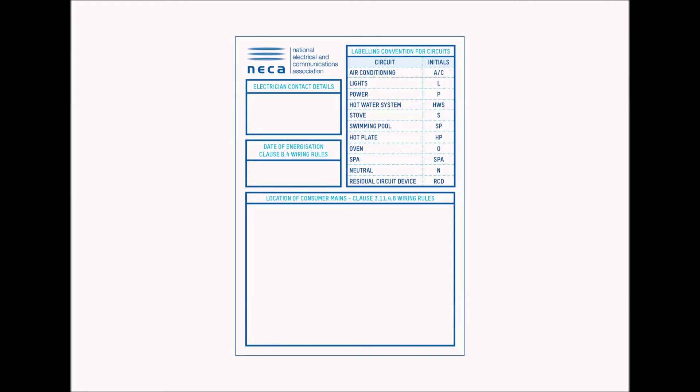Western Power have informed us that the main issues are incorrect labeling and no fire sealing of switchboards, and we have some simple solutions to help you stay compliant. NECA WA offers this sticker to members for free — it meets the wiring rules requirements by clearly displaying the circuit legend.